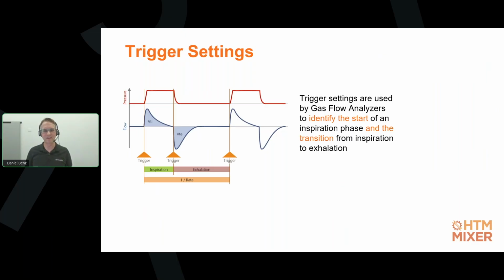In a typical testing application where a ventilator is connected to your gas flow analyzer and test lung, you will see flow and pressure waveforms. They will probably look like they are displayed here on this slide. So trigger settings are used by the gas flow analyzer to identify the start of an inspiration phase and then the transition from inspiration to exhalation. In most analyzers, you will always see two sets of settings. One is most likely called the start trigger, and the other one is most likely called the stop trigger or the end trigger. So this always relates to the inspiratory phase. The start trigger is used to determine the start of a new inspiration, which means a new breath. And then the stop or end trigger is used to determine when it transitions from inspiration to exhalation.